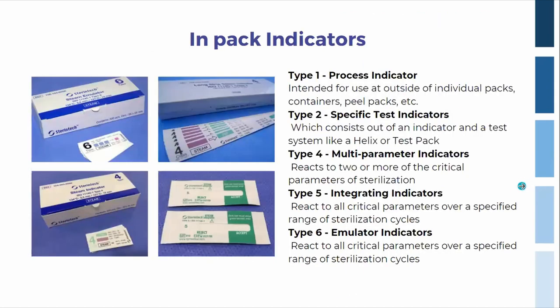I just want to look at the different types. I've been talking about type 4, type 5, type 6, so the types might be overwhelming. So I'll just go through them one by one. Type 1 is a process indicator. It is intended for use on the outside of individual packs, containers, or peel packs. So a typical type 1 indicator will be the indicators on the side of your sterilization wrapped packs. That's a type 1. It doesn't mean that it's met all the parameters. It's just indicating that it has gone through the autoclave. So working on that, you can't say that it has passed or that the pack is sterile.